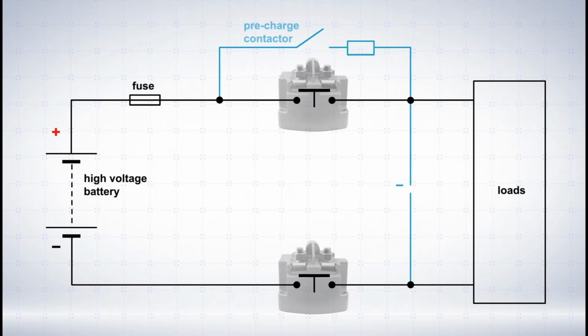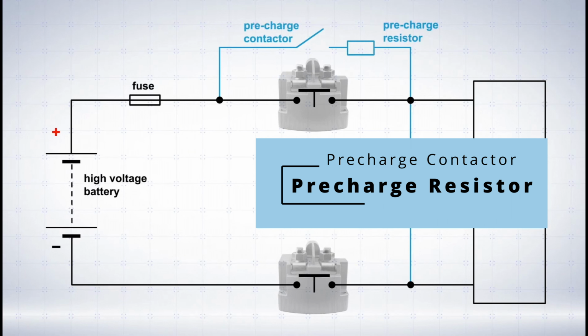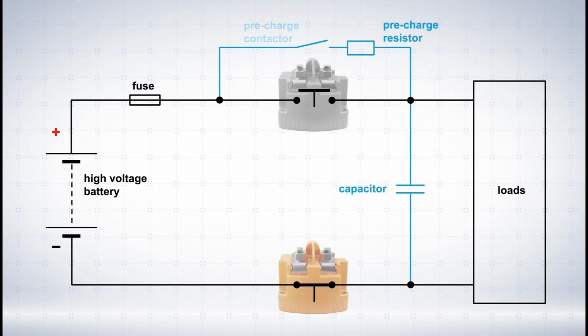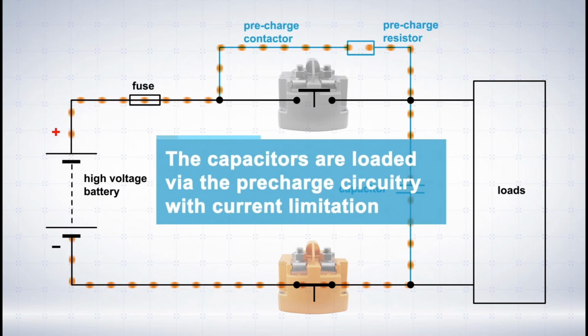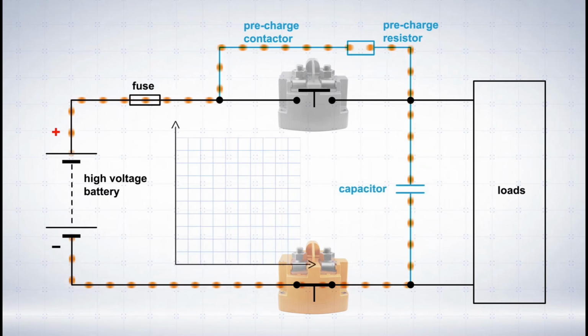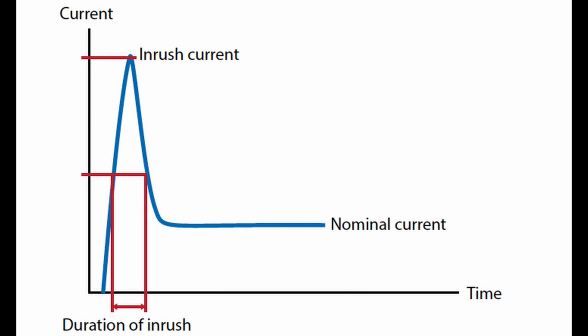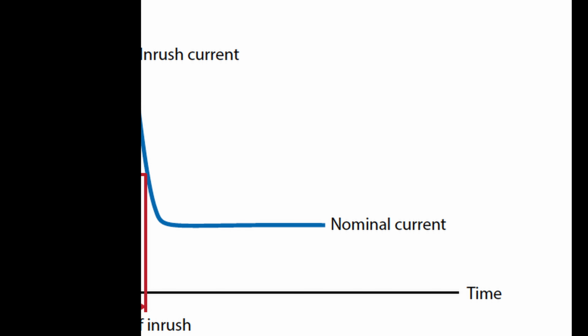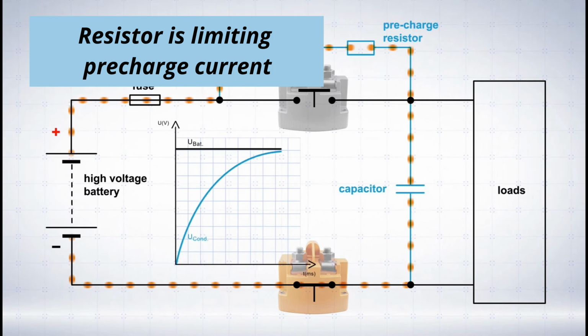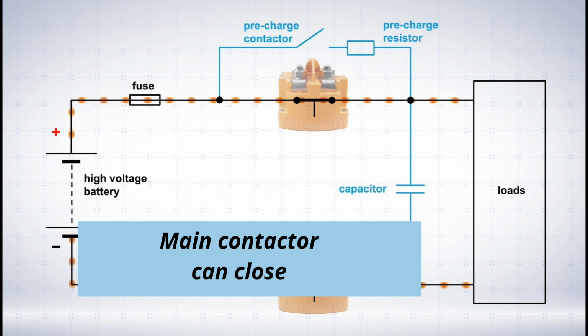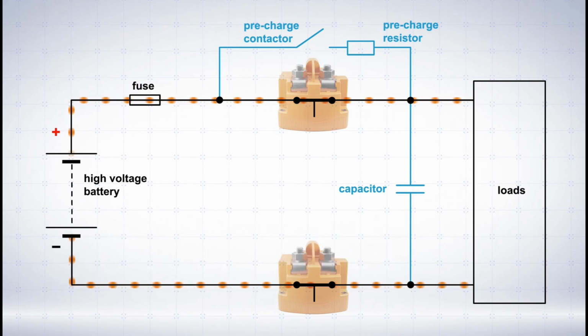At this point I think I owe you a brief explanation of the pre-charge resistor and pre-charge contactor. So why do we need a pre-charge resistor? Because we have rather big capacitors inside the inverter. When we apply the voltage, the capacitance will generate really high inrush current, and this inrush current will weld the contactor closed shut. So to minimize the current, we basically put it through the resistor first, and that's why we have a pre-charge circuit. So once the capacitors have been fully charged, the pre-charge contactor can open and the main contactor can close.